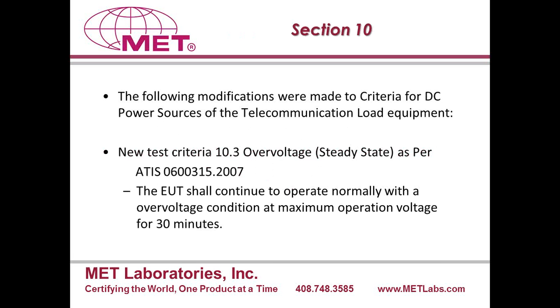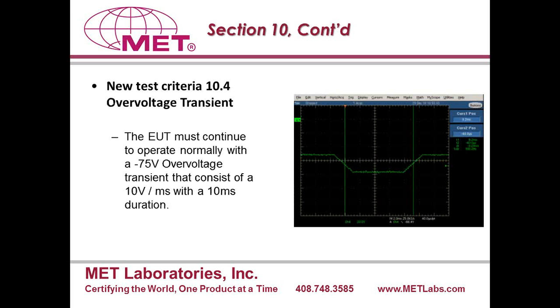Several modifications. The very first modification is the addition of the criteria, which is added as criteria 10.3, the over voltage requirement. With this new requirement, the unit has to operate under normal conditions for 30 minutes at the maximum voltage specified by the ATIS document for the operating voltage of the device, whether it's a 48 volt or 24 volt system or whatever that may be.